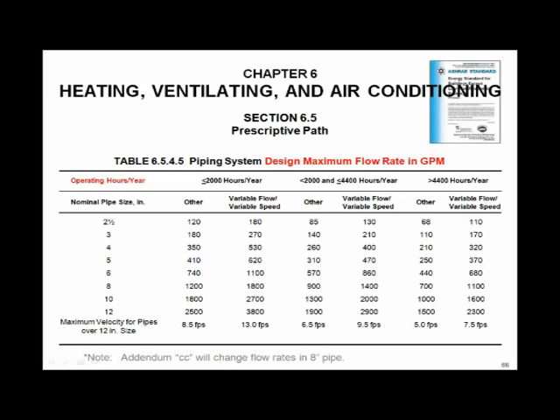But take note, it would allow you to have smaller pipe sizes for variable flow than constant flow. In other words, the same size pipe on the variable flow can handle more GPM than on the constant flow. Look at the hours of operation. The more hours of operation, the bigger the pipe, or the smaller the flow. In other words, they're looking at it from a standpoint of operating cost based on pipe size and flow. And variable flow gives you smaller pipe sizes. This is why it's important you begin, again, to understand the impact. How are you going to deal with this? And you've got to do a detailed pump head loss calculation, and you've got minimum pipe sizes on condenser water piping. That is brand new.